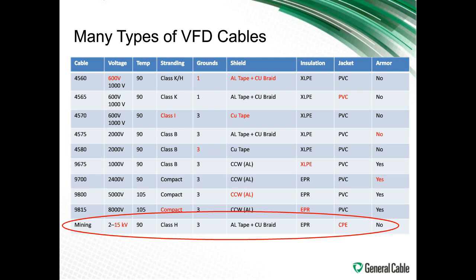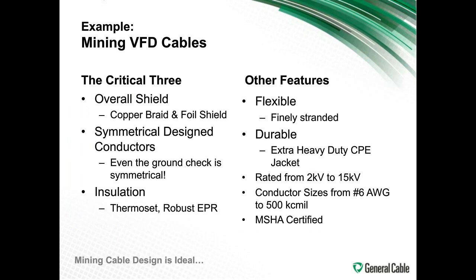So altogether, you get this better insulation material, you get a really good shield with the aluminum tape and a copper braid, you have symmetrical grounds, and you have a whole range of voltage possibilities, 2 kV to 15 kV. So in the mining cable, the critical 3 are taken care of. You have an overall shield, symmetrically designed conductors, and even the ground check, which is symmetrical, and you have a very good, robust thermoset insulation in the EPR. Other features: it's flexible because of finely stranded conductors. It's very durable, and we have conductor sizes from 6 to 500 kcmil, and it's MSHA rated, certified.